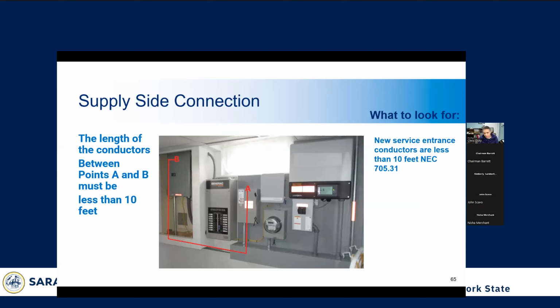Another thing in the 2017 NEC, which is the one that's adopted in New York State, it states that the length of the supply side conductors can be no longer than 10 feet unless other means are taken to protect them, such as current limiting devices. You can see here, A is where the inverter output is fused and changed to service conductors, which are the 60 amp rated conductors. And they go to the breaker panel and connect in on the supply side of that main breaker. And so that total length from A to B can't be more than 10 feet.